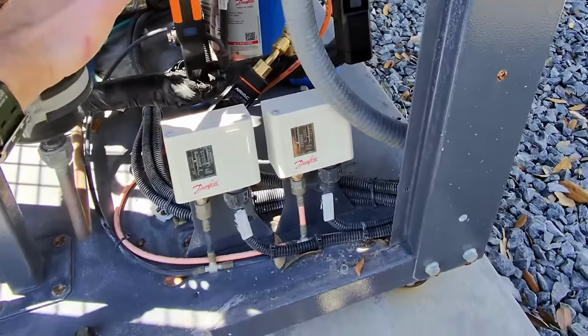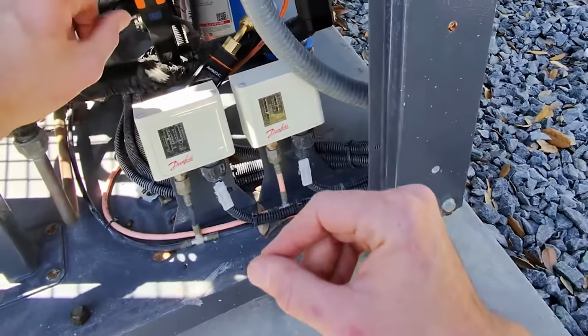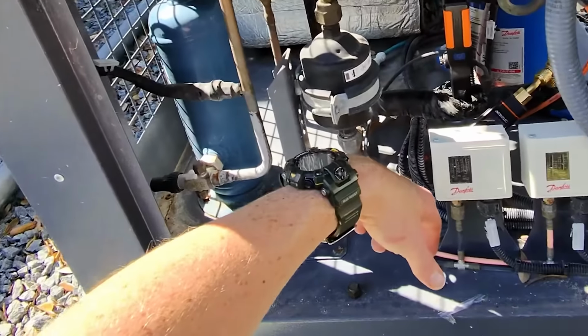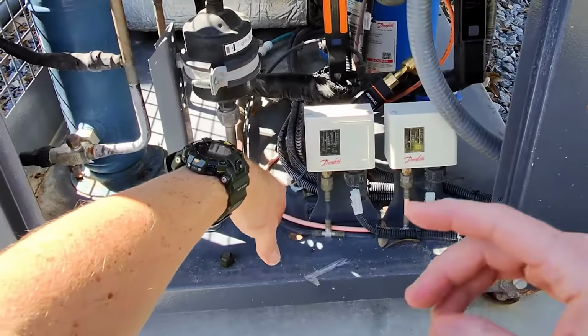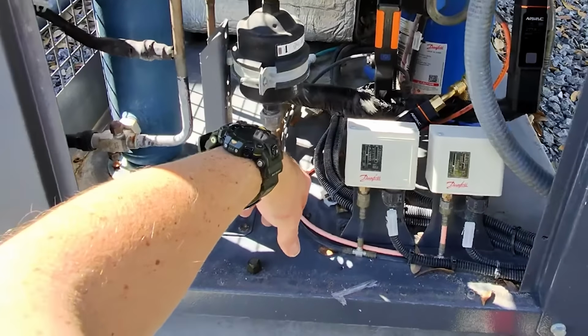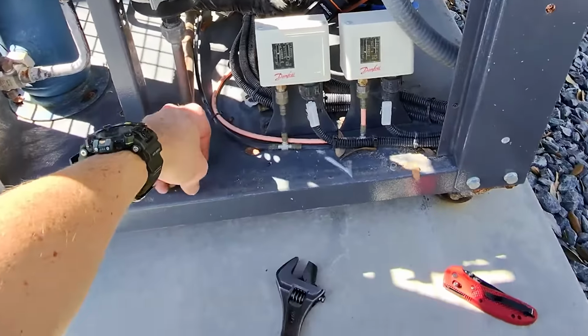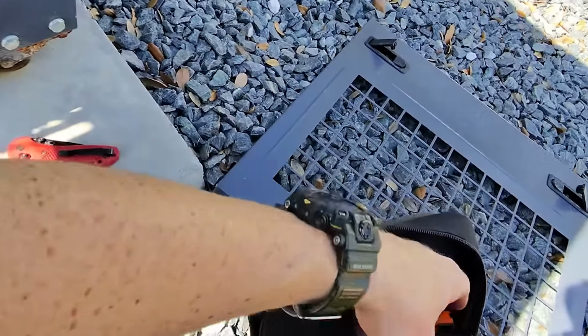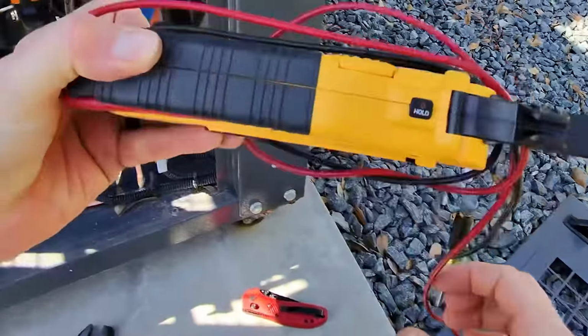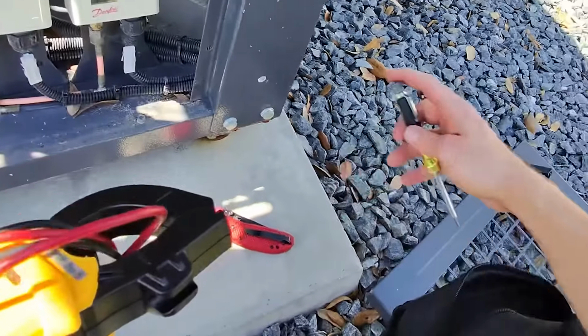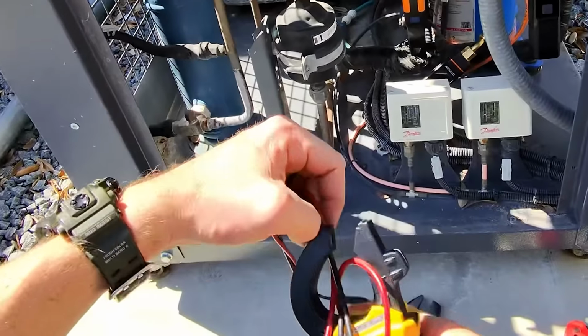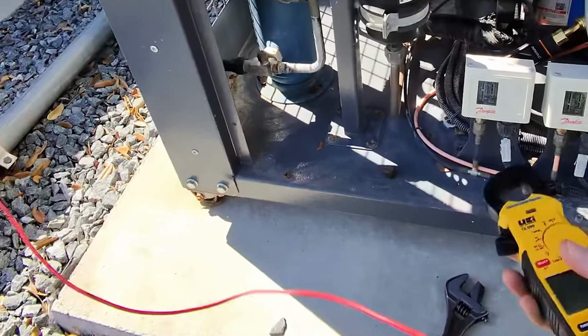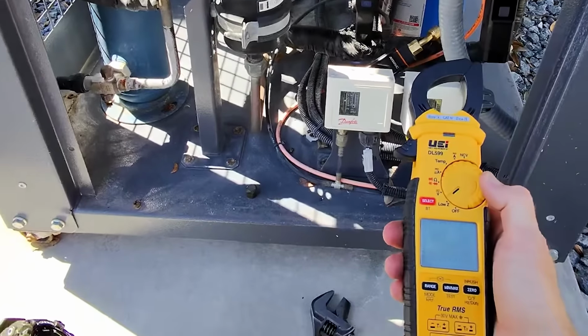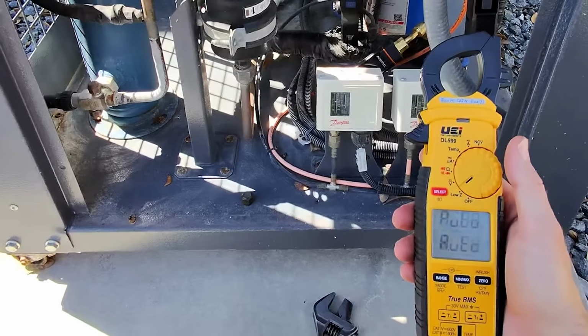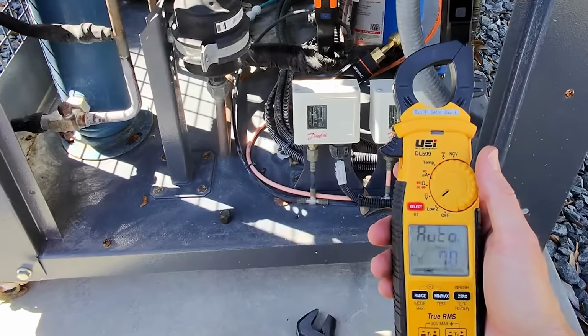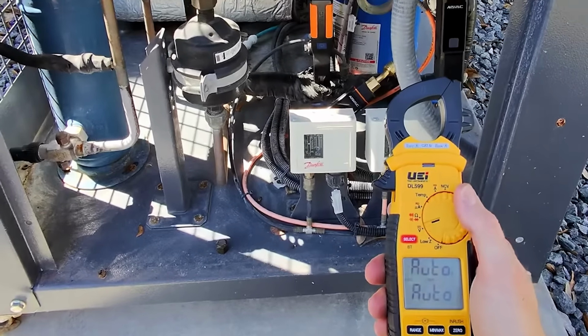And the way to check that, after we've gauged up like this and checked a few things to make sure one's not flat, nothing going on with the refrigeration system, is to now check the amp draw of the water pump compared to nameplate amps to ensure that we are in fact within the range, because for all we know, it's just got bad bearings in such a short period of time. And that is the reason that it is not operating correctly. So let's pull out our UEI meter and do some testing.